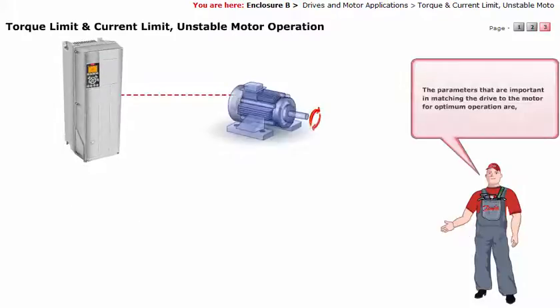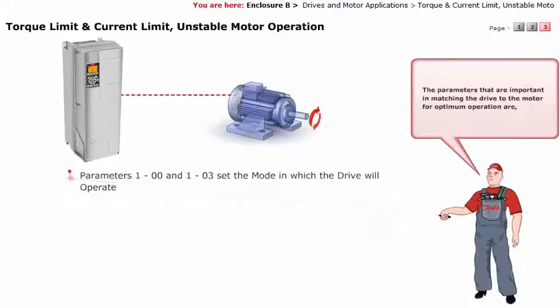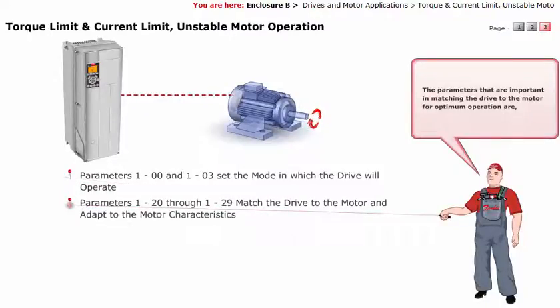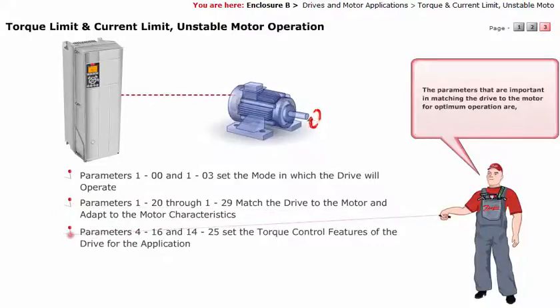The parameters that are important in matching the drive to the motor for optimum operation are: Parameters 1-00 and 1-03 set the mode in which the drive will operate. Parameters 1-20 through 1-29 match the drive to the motor and adapt to the motor characteristics. Parameters 4-16 and 14-25 set the torque control features of the drive for the application.